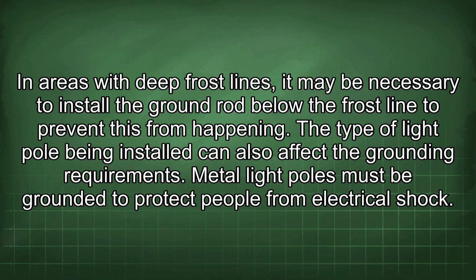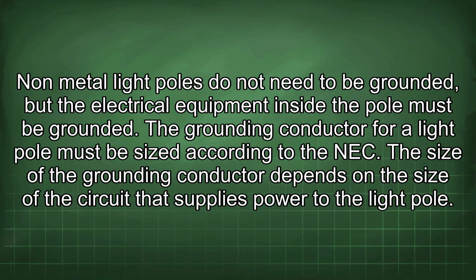Metal light poles must be grounded to protect people from electrical shock. Non-metal light poles do not need to be grounded, but the electrical equipment inside the pole must be grounded. The grounding conductor for a light pole must be sized according to the NEC. The size of the grounding conductor depends on the size of the circuit that supplies power to the light pole.